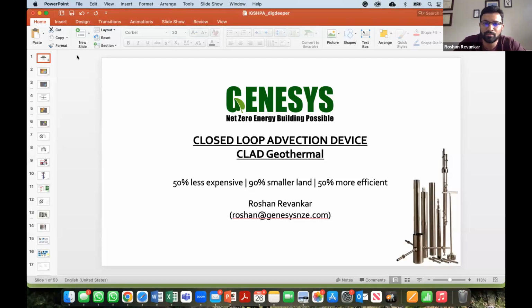Excellent. Mike asks, if a closed loop system is below the frost line and enters the building, why is propylene glycol needed? Steve responded in the chat, you're correct, it would not have to be. It's up to the engineer to decide if they need glycol. Of course, the system will work even better with just water inhibitors. Any comment on that, Roshan?